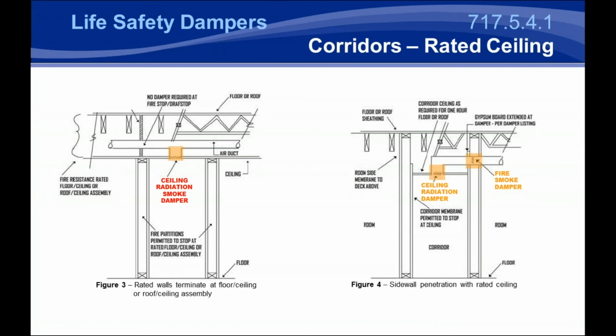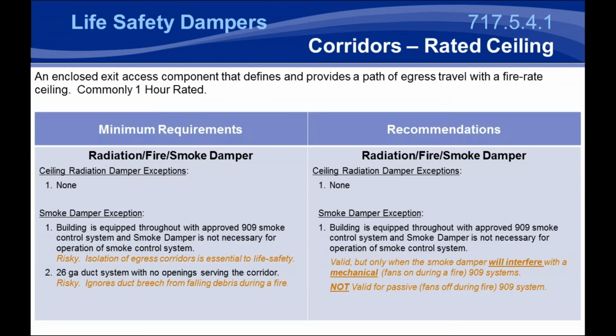When you've got a rated floor ceiling assembly that's wood stud or wood joist type construction, basically any combustible type of assembly, it is going to need a ceiling radiation damper that is specifically stated to be allowed in that assembly. And we'll talk about the different types of ceiling radiation dampers, but typically what we recommend is that figure 4 type of orientation, where you've got a ceiling radiation damper protecting the ceiling membrane and a fire smoke damper protecting the sidewall of that rated corridor. You can use the same types of exceptions that we talked about earlier, so I won't go through that again.